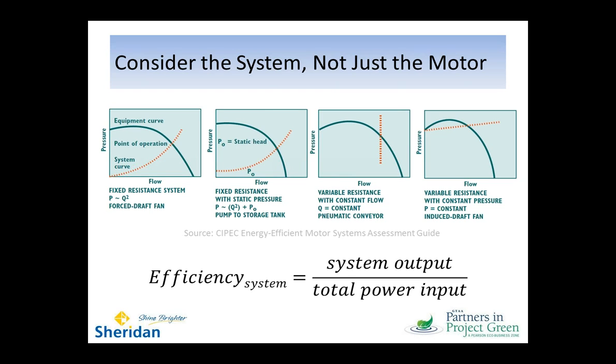But in all of these cases, the pump curve in blue is trying to intersect that system curve at the point of maximum efficiency. So all of our components in the system have their own efficiency curves, and obviously we want them all operating at maximum efficiency. There are a few different scenarios that push us away from this optimum point. Since we're often sizing our rotating machinery with a safety factor, making it a bit extra large just in case the system requirements change, or just to make sure the thing doesn't come in underpowered, we're automatically pushing the motor curve off that maximum efficiency point. We're then either running that motor at a lightly loaded condition, which we'll see later is not really the most efficient setup, or we find that we need to control the system to align the curve to the motor.